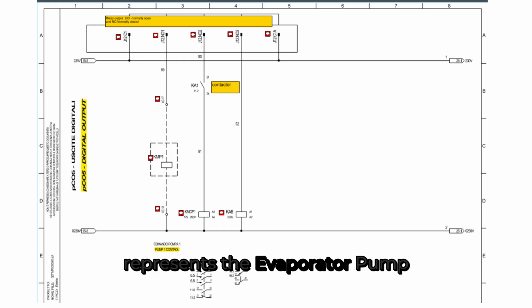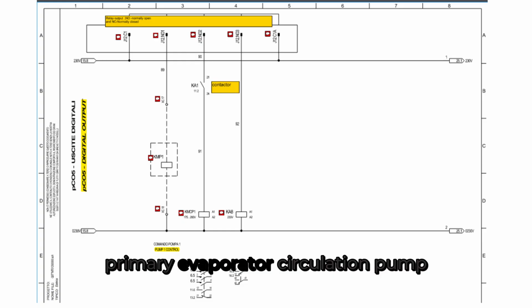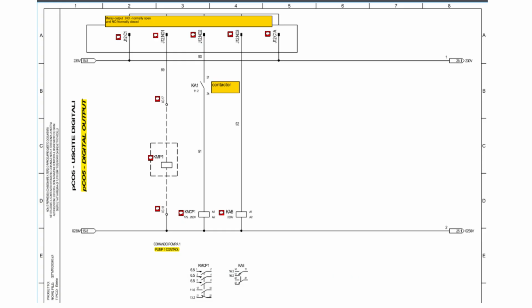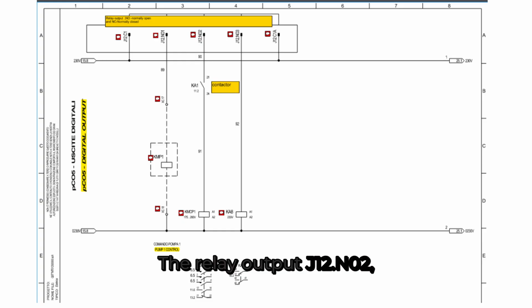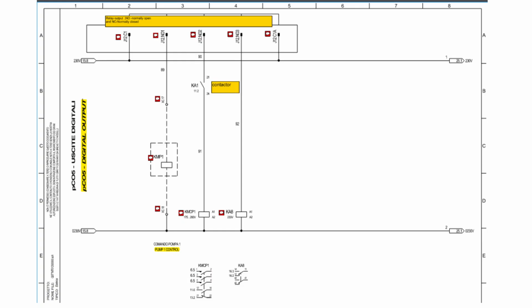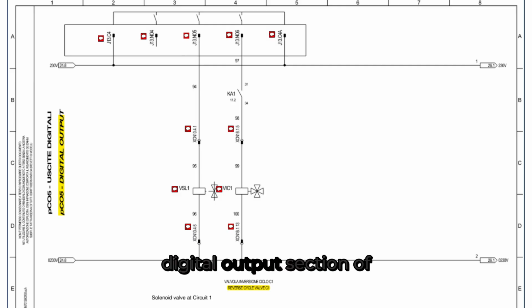D12-1001 represents the evaporator pump 1 control circuit, which manages the operation of the primary evaporator circulation pump in the system. The relay output J12.NO2 energizes the KA1 relay coil for the compressor contactor coil for circuit 1, KMCP1. You can see another relay coil labeled KA8 at the relay terminal J12.NO3 for opening or closing the motorized isolation valve at the evaporator. This page continues the digital output section of the Carel pCO5 controller.